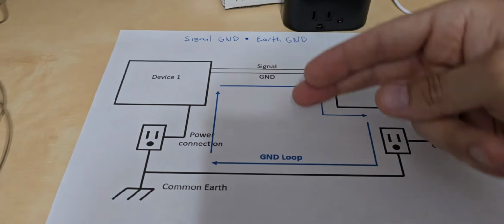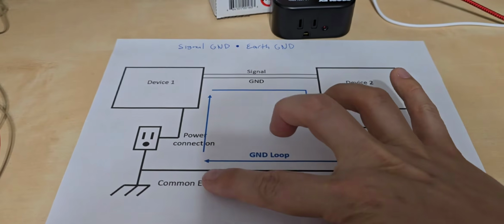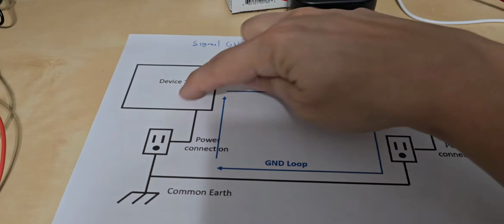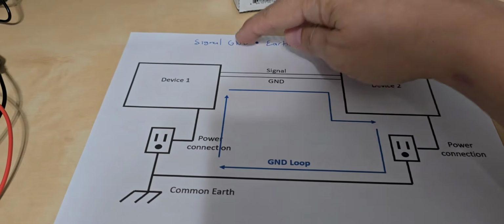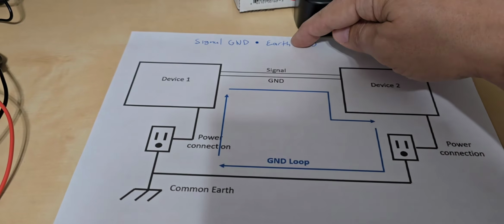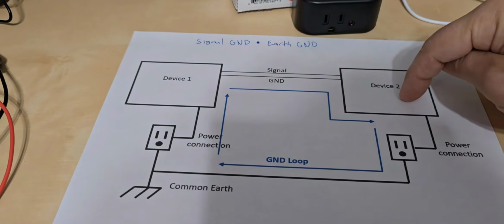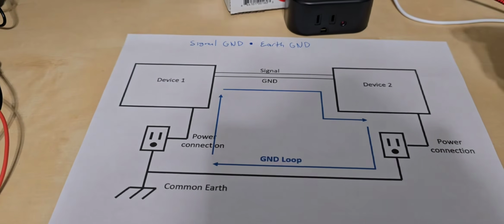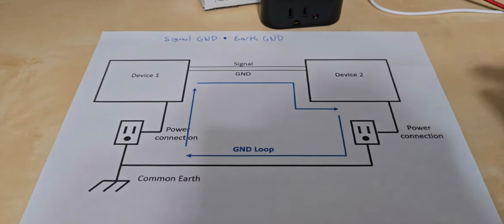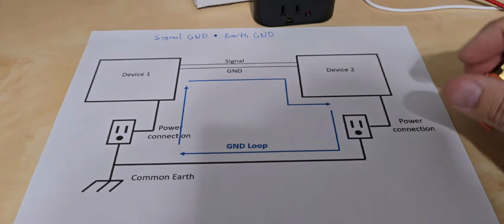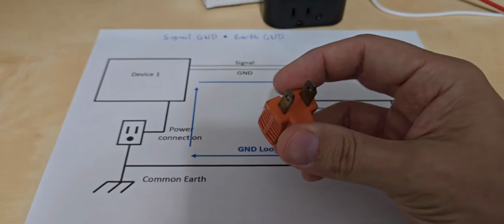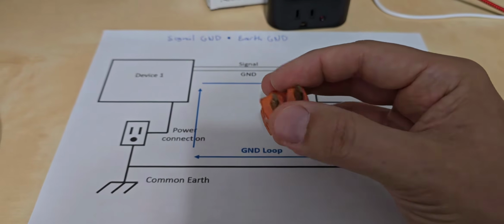Or if you don't have the ability to do that, you have another way to isolate the earthing pin from your signal ground. In each of these devices, signal ground is tied back to earth ground at one point, and that can never be broken—because if you were to lift one of these pins using one of these cheater adapters, as they call them, it takes the 3-pin plug and breaks the 3rd pin, so now you just have your hot and neutral.